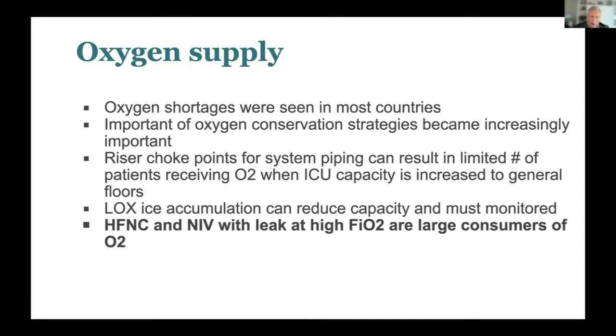So if you try to convert that into new ICU bed space, you'll find out you can't run 3 or 4 high flow nasal cannulas from that oxygen system. It causes the alarms in the wall to go off because it's drawing too much flow.